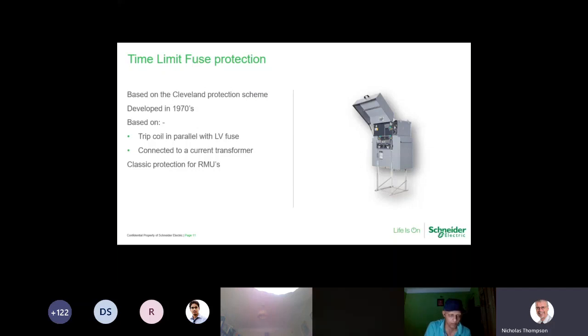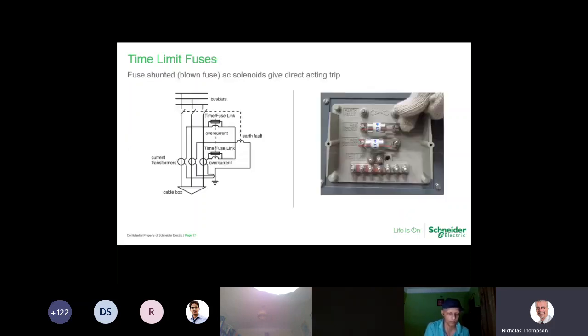It's very much the accepted norm with ring main units for the DNOs. You could probably say that about 80% of all ring main units that the DNOs use will use time limit fuse as their protection. The remaining 20% are going to be used for traditional protection relays like VIP or the Micom P116. There is actually a CIRED paper on this form of protection, so internationally it is known but not widely used outside of the UK.